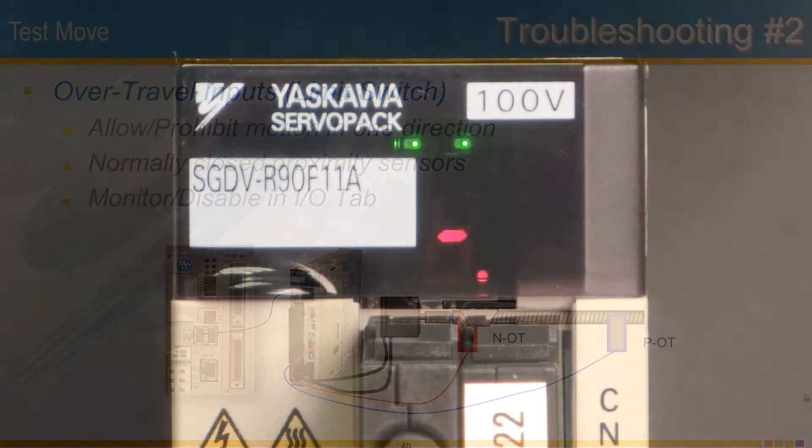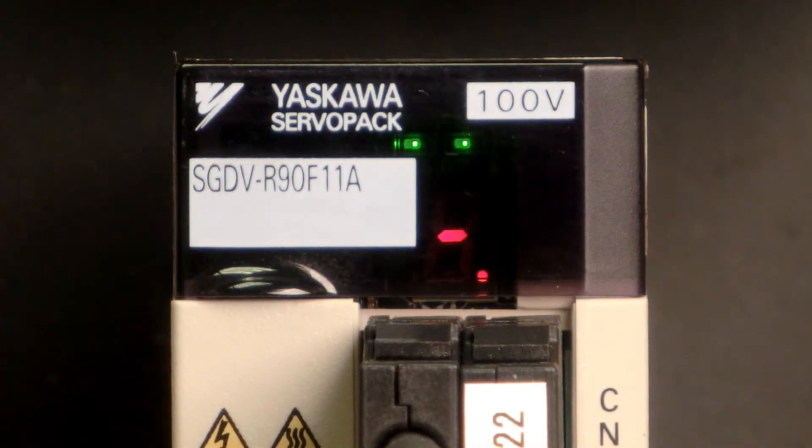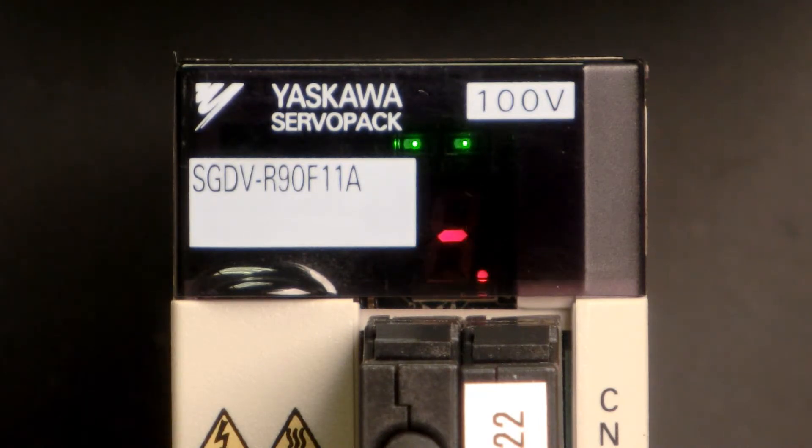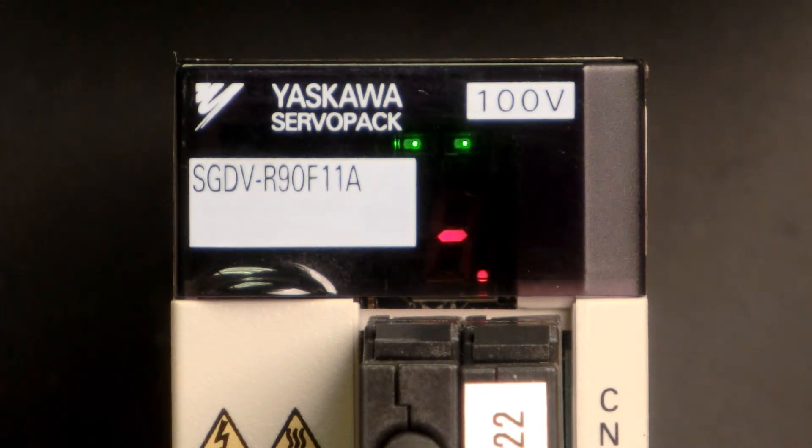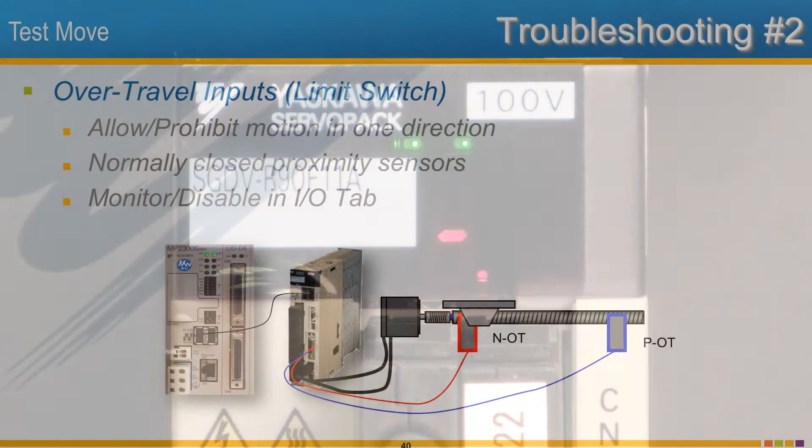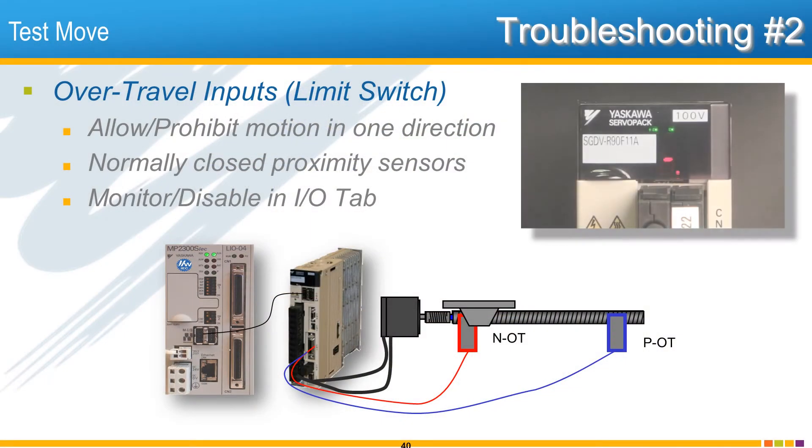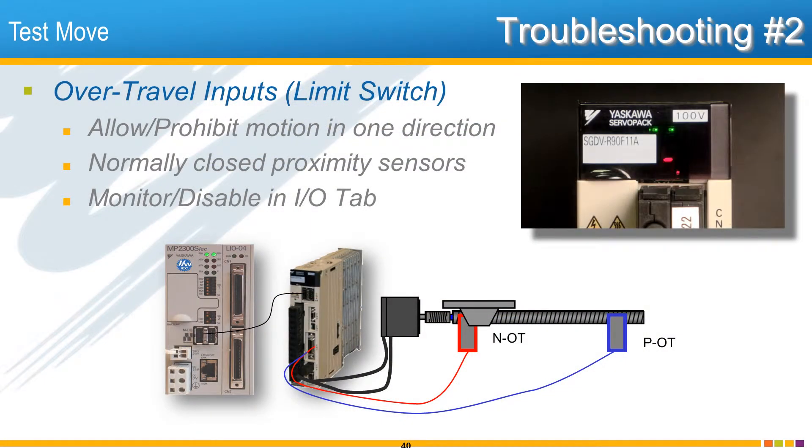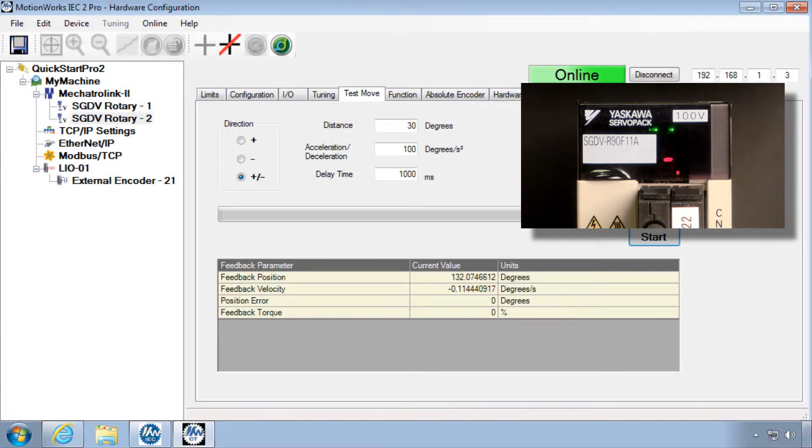Over-travel will be indicated on the Sigma-5 front panel as P and N for positive and negative motion prohibited. If you attempt a test move in the prohibited direction, the motor will enable but not move.